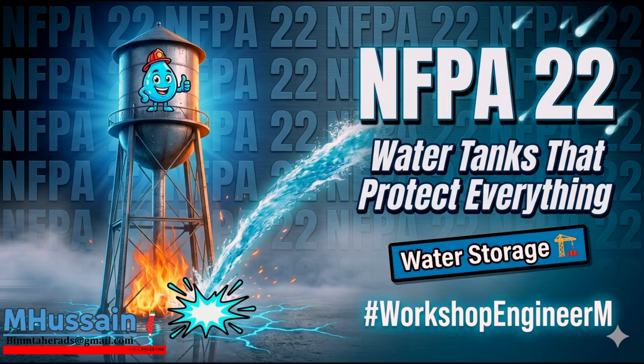Now, there is another tiny, highly specific detail regarding the pressure tank's nameplate. Section 7.1.8.2 requires a metal nameplate with raised or stamped letters showing the manufacturer, year, capacity, and working pressure. But Section 7.1.8.3 mandates that this nameplate must also serve as the actual water level indicator, bearing an easily observed raised arrow. Right. Why mandate a raised metal arrow on a riveted plate? Why not just paint a fill line on the side of the tank or use a heavy-duty industrial sticker?